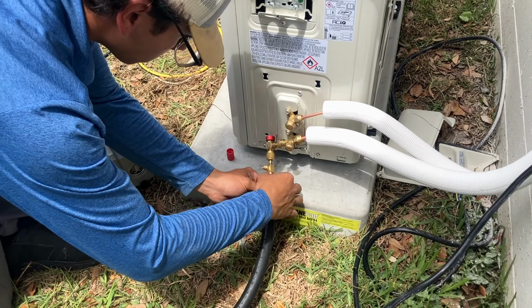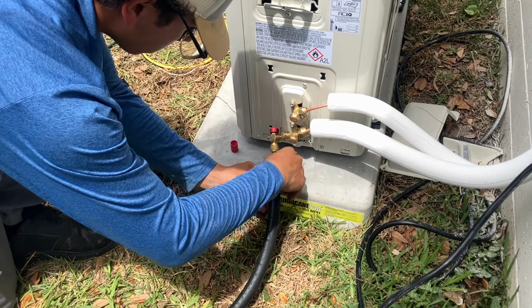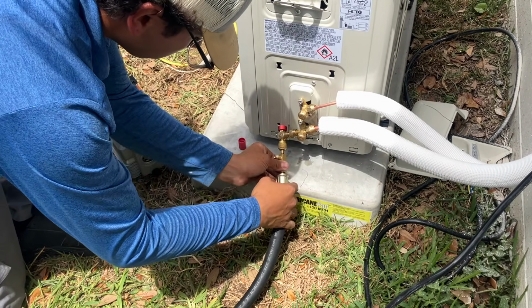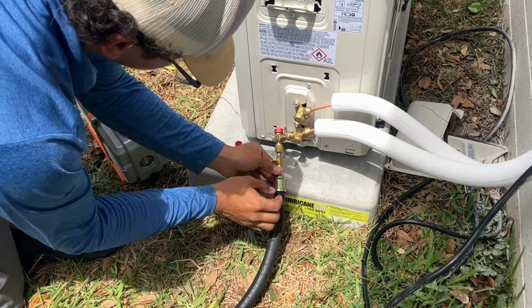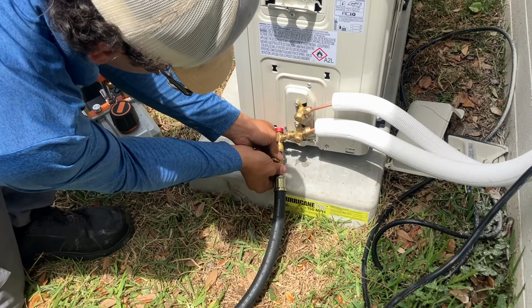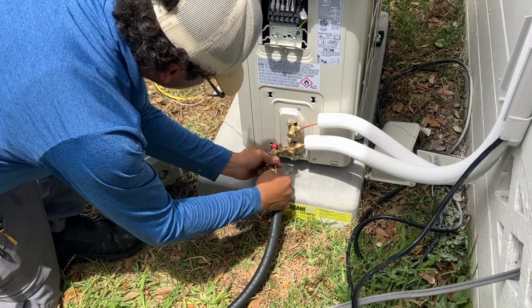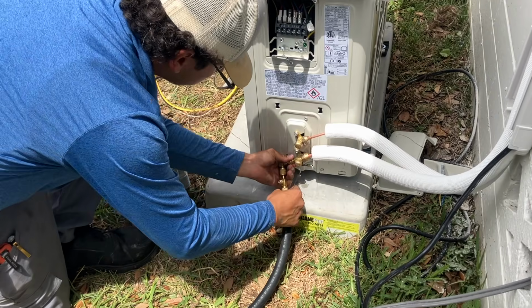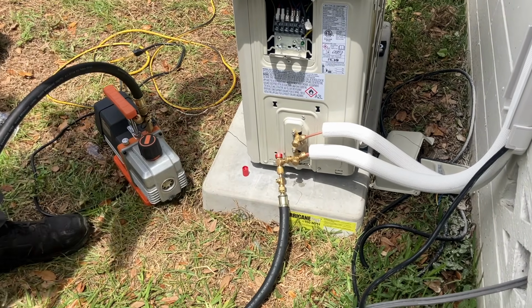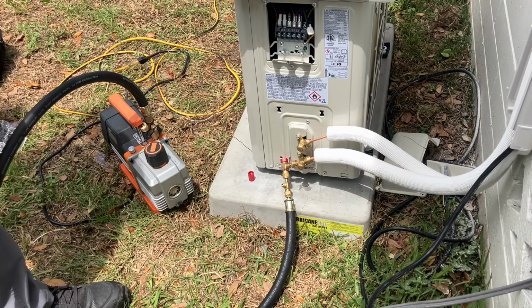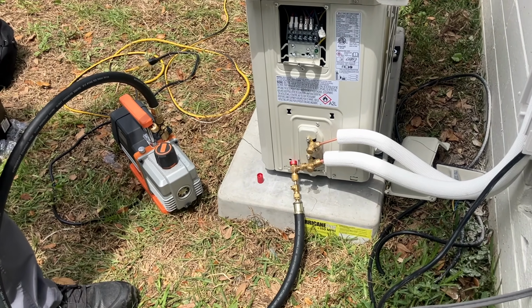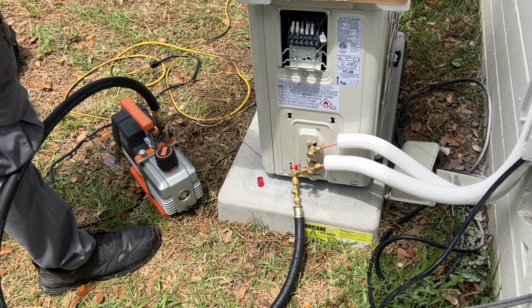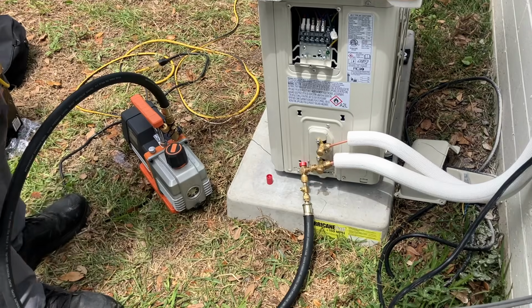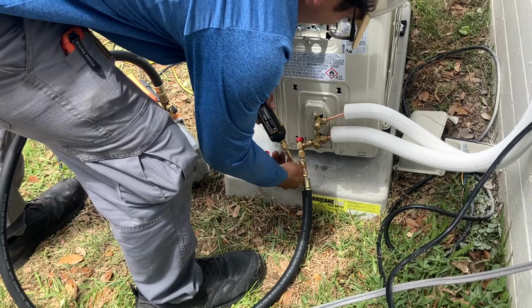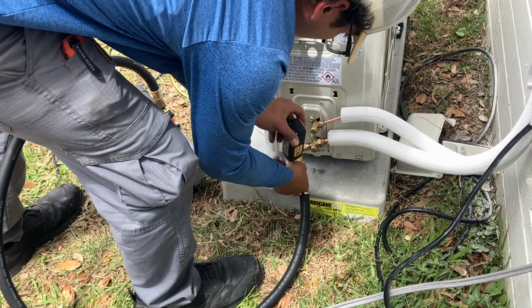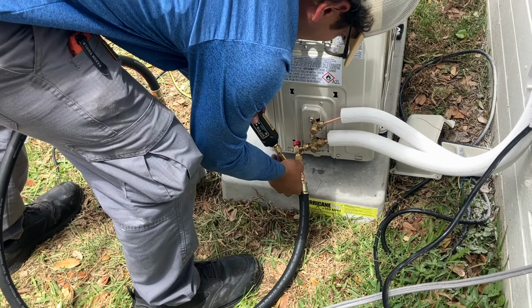It's nice that he has plugs inside on the hoses to keep the moisture and atmosphere out of them. That hinders the time it takes to vacuum down a system—all that moisture and atmosphere. Think about it, folks: when you're pulling down a vacuum, you're pulling into negative atmosphere, so any moisture in the system is going to boil off. And we all know what happens with water when it boils off—it expands like 14,000 times its mass when it turns into vapor, into steam. So moisture boils off and it expands, and that increases the time to bring your levels down below 500.